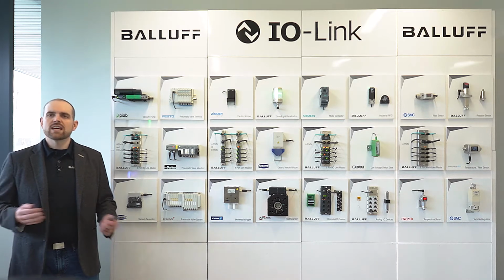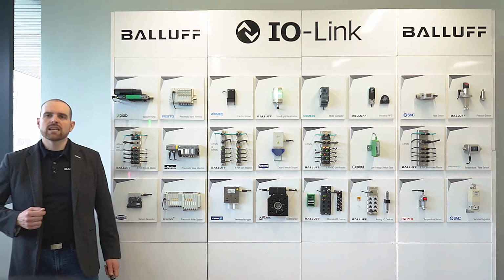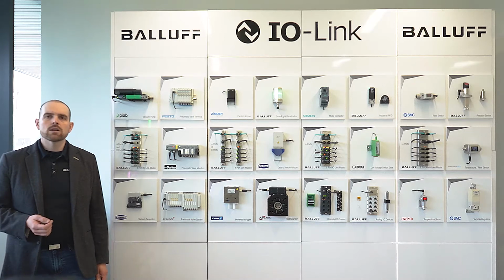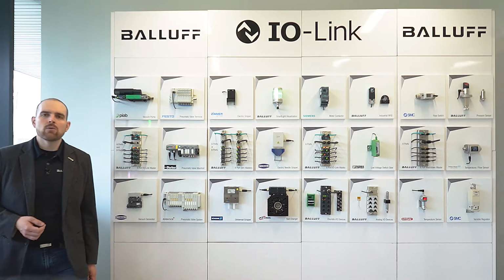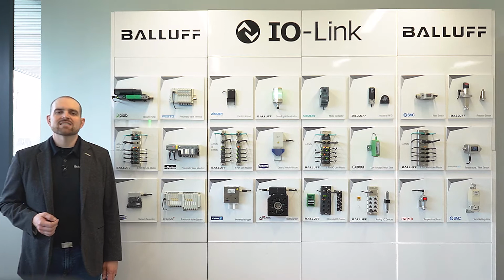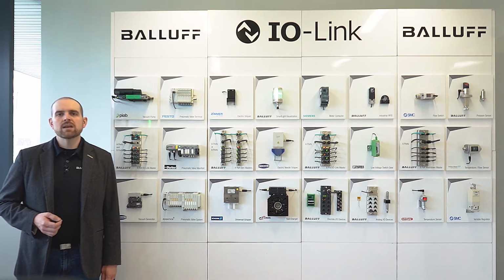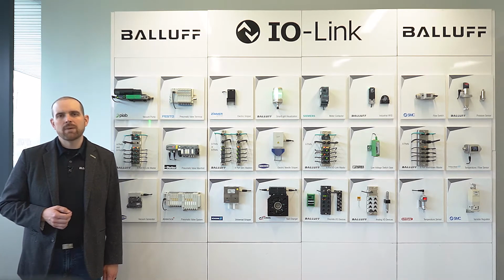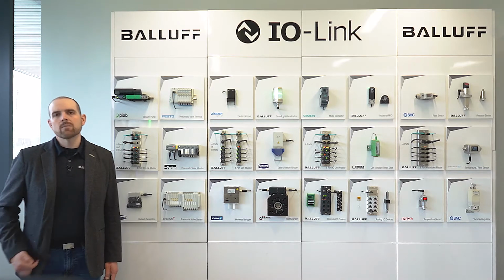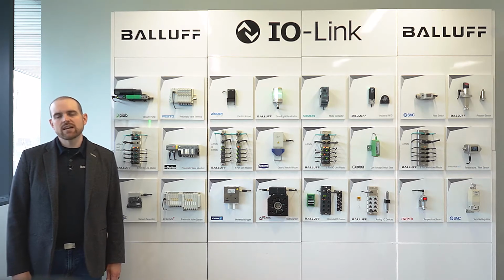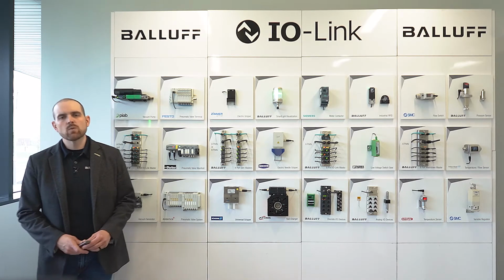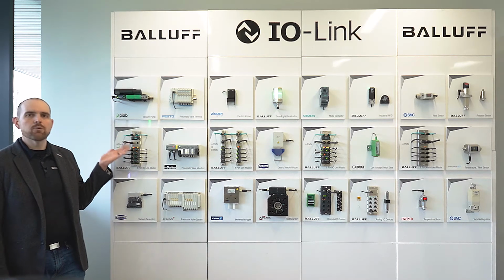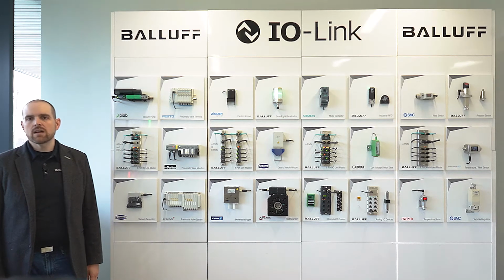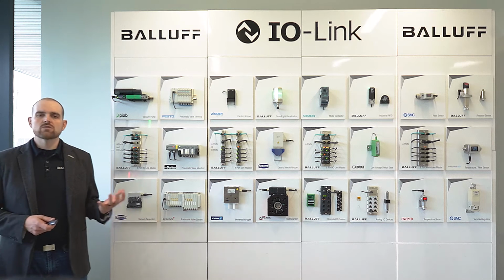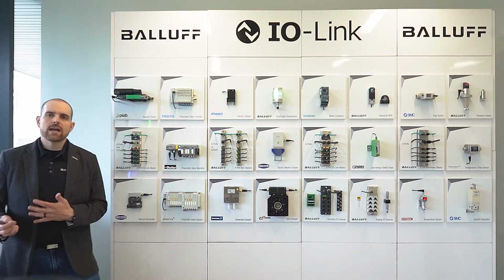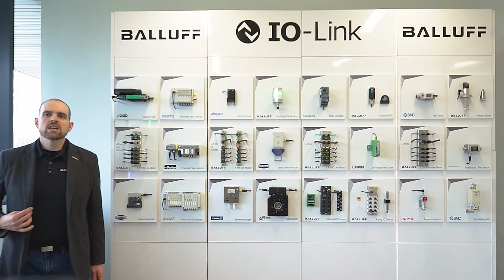It's important to know the type of port and the type of device you're plugging in, because a B port allows you to control output power. It uses pin 5 as a second ground and pin 2 as output power, isolated from the IO-Link communication and the IO-Link device power. This is nice because it lets us safely control outputs, like the devices here on the left side of our demo. So A ports use 3 wires, and B ports use 5 wires, with those extra wires giving you output control.